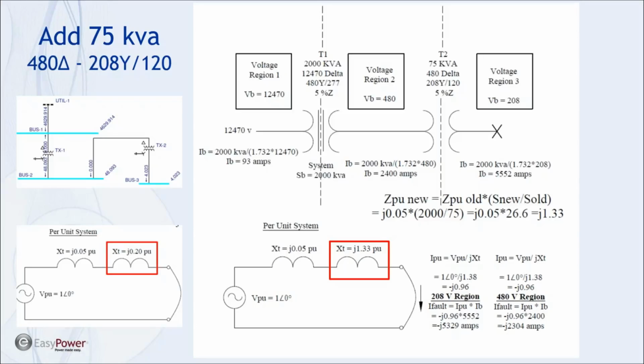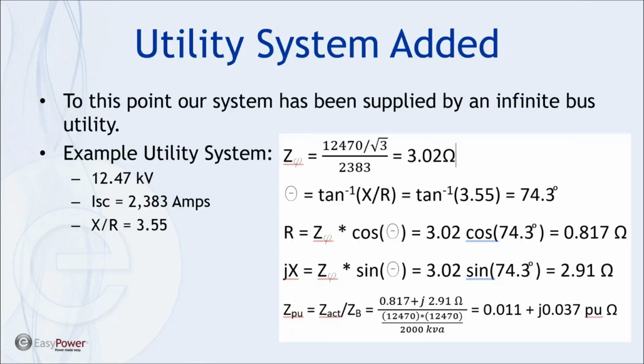Okay, the last thing I have on the agenda to talk about is what happens when we have a utility system that's not ideal, not an infinite bus. Here's an example from a job I did last year. In our area, we are served by First Energy and American Electric Power. They have a lot of 12470 distribution voltage. I contacted the local power company at one of my facilities, and this is the three-phase characteristics they gave me. The serving voltage was 12470, their available short circuit capacity was 2383 amps, and the X over R ratio is 3.55.